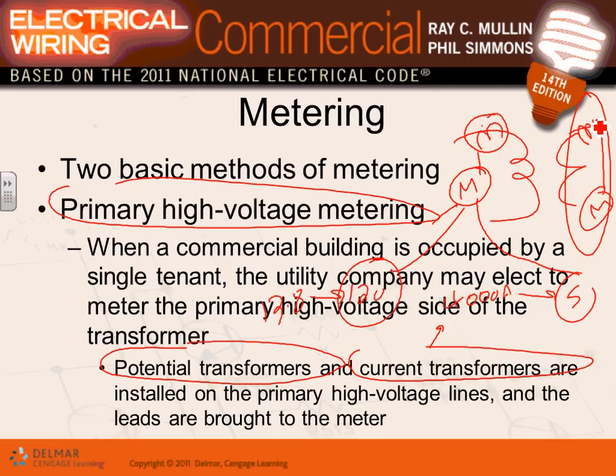Why would they be metered at high voltage? The only time they do it is if the customer wants 13,800 volt coming to their building to feed different equipment at that 13,800. That's what you meter. Typically, 5% of the people. You're talking about major manufacturing. Very huge equipment, melting steel. So that's the only time you have high voltage metering.